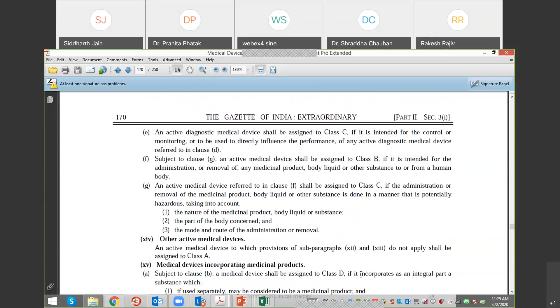So here you can see point number C. An active diagnostic medical device shall be assigned to class C, which is intended for the monitoring of vital physiological parameters, where the nature of any variation is such that it could result in immediate danger to the patients. If your standalone software as a medical device is used for the monitoring of vital physiological parameters, and it has a direct impact on the health of the patients, like cardiac performance, respiratory activity or the central nervous system, and it will lead to an immediate danger to the patient, then you can classify them into class C devices. But if it is just used for a normal diagnosis purpose and it does not have a direct impact on the health of the patient, then you can classify them into class B devices.